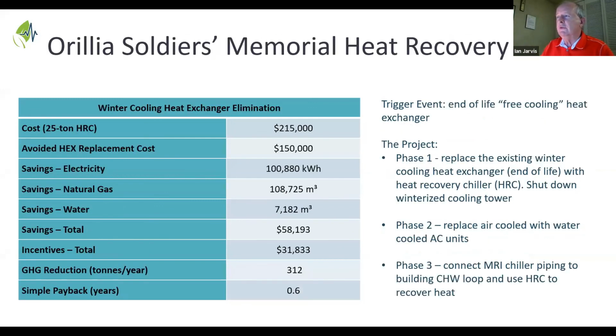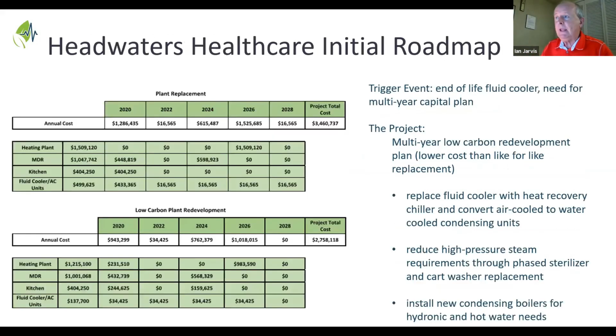Orillia Soldiers Memorial, the trigger event, is the free cooling plate exchanger that interfaces between the chilled water system and a winterized cooling tower in winter. It's at end of life, it's plugged up, it's in terrible shape. The project here is, instead of paying $150,000 for the heat exchanger, spend $215,000 on a heat recovery chiller, and then over time, add more and more equipment to that. And you can see the economics of the low carbon solution are often very attractive indeed.